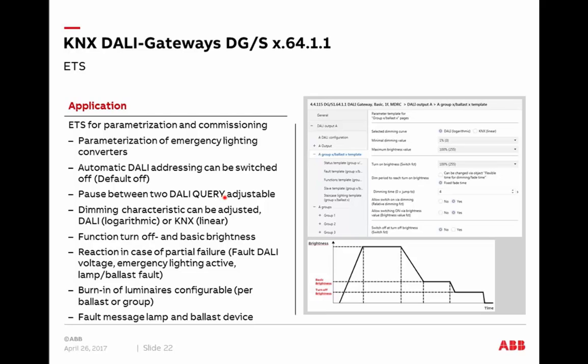Another new feature is the adjustment of the pause time between DALI query commands. DALI is a master-slave system where the DALI gateway continuously asks devices about their brightness value and availability. For some special DALI ballasts where the standard speed of sending query commands is too fast, we can now increase this time directly in the ETS parameters — based on feedback from practice in the market.